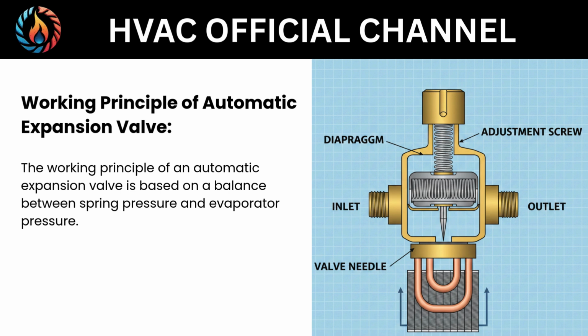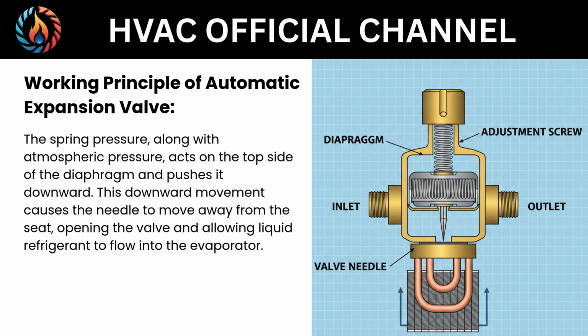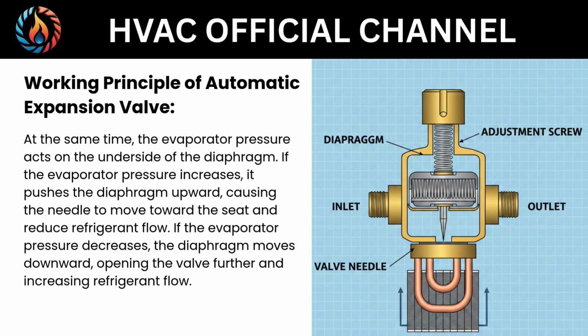Working principle of automatic expansion valve. The working principle of an automatic expansion valve is based on a balance between spring pressure and evaporator pressure. The spring pressure, along with atmospheric pressure, acts on the top side of the diaphragm and pushes it downward. This downward movement causes the needle to move away from the seat, opening the valve and allowing liquid refrigerant to flow into the evaporator. At the same time, the evaporator pressure acts on the underside of the diaphragm.